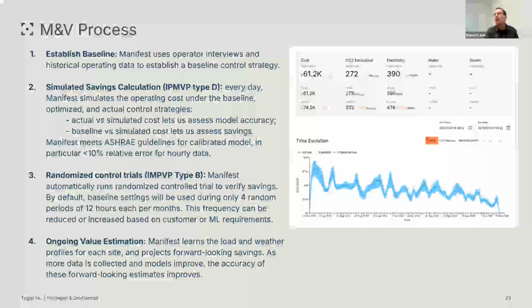We consider safeguards to be in place, with limitations that our operators can have input on, like how quickly we're allowed to change the set point. One limitation is that we typically change it at most once per hour. That's the default setting, and it's rare to have a system where it would be advantageous to do it faster, because of feedback times. On top of that, we also have a limitation on how much the set point can change within that hour. Really, it's mostly the feedback times in the system that determine that, not so much the control logic, because in the end fans need to ramp up and water temperatures need to mix and change. But there are several levels of settings that we discuss with each system operator to get input on.